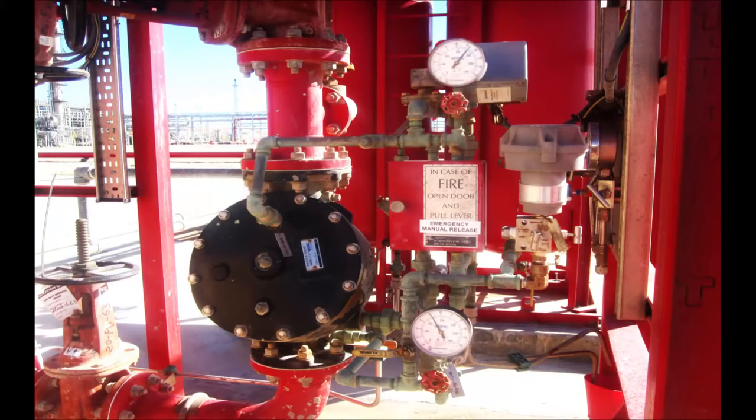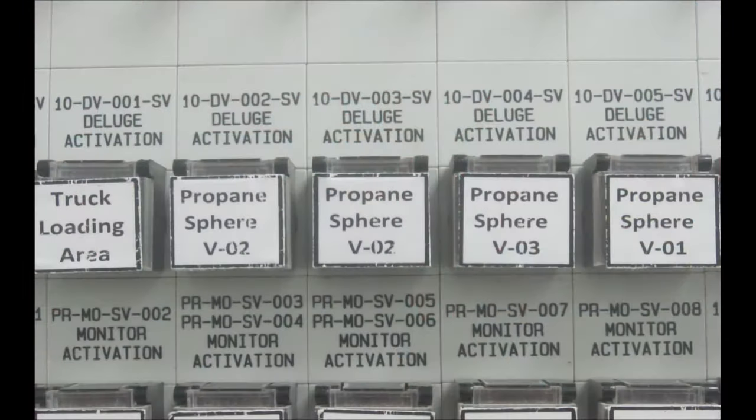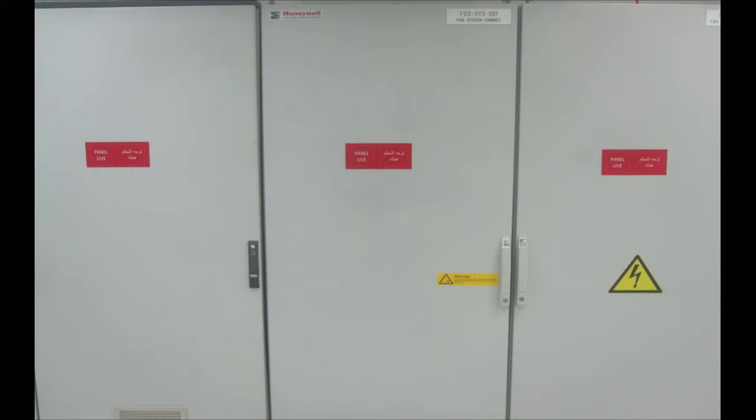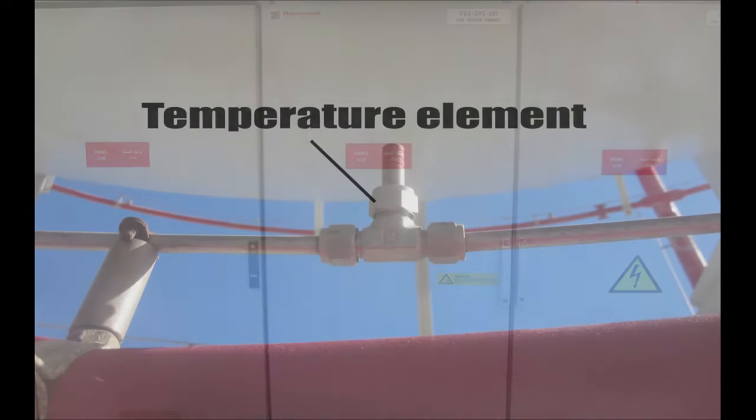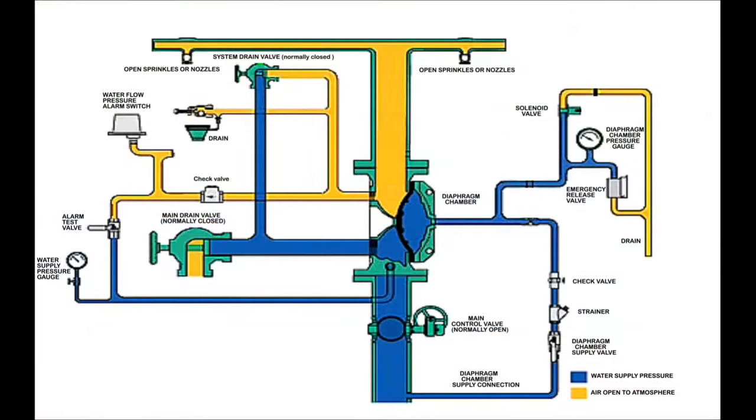There are several methods for operating the deluge valve system, all of which depend on depressurizing the priming water pressure to open the deluge valve. The deluge valve can be operated manually using the emergency release valve that is present on the priming loop. Another method for activating the deluge system is by activating the solenoid valve, which is also present on the priming loop. This can be activated either manually by a push button in the control room, or automatically from the fire and gas panel in case a temperature element senses high temperature on the protected equipment.